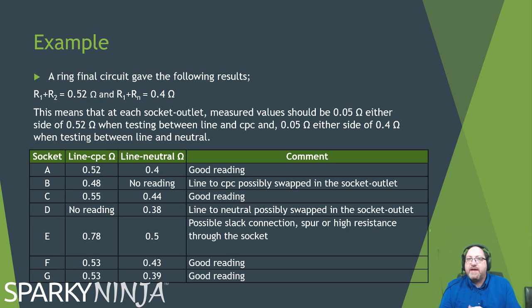So, this little table, for example, a ring final circuit gives the following results. You have an R1 plus R2 of 0.52 and an R1 plus Rn of 0.4. Makes sense. This means that at every socket outlet, the measured value should be 0.05 either side of 0.52 ohms when testing from line to earth, R1 plus R2, and it should be 0.05 either side of 0.4 when testing between line and neutral, R1 plus Rn. 0.05 is our tolerance for connection resistances. If we go beyond that tolerance, then we're basically going into guess-who's country. We don't know where we're going. So we stay within 0.05 tolerance up and down.